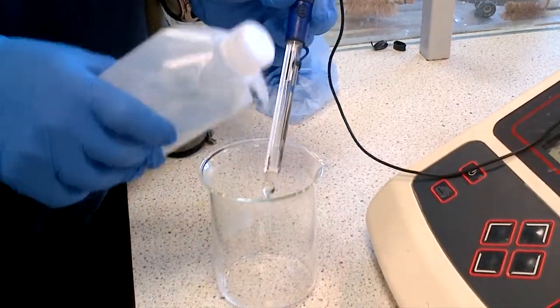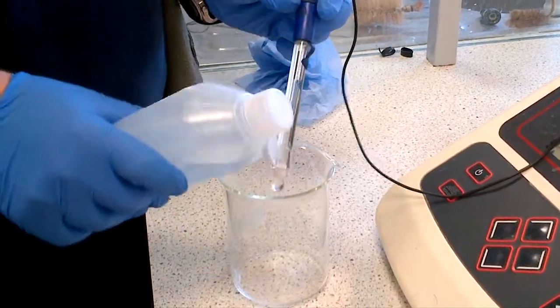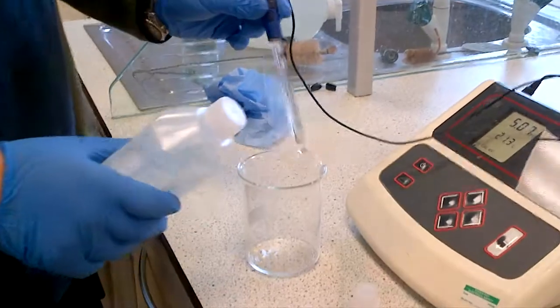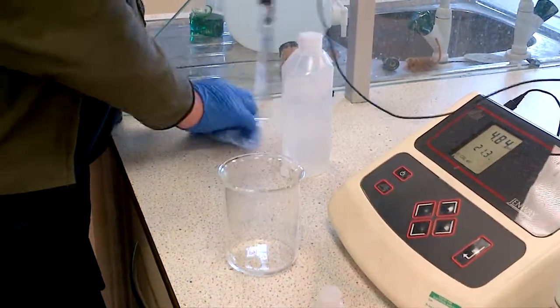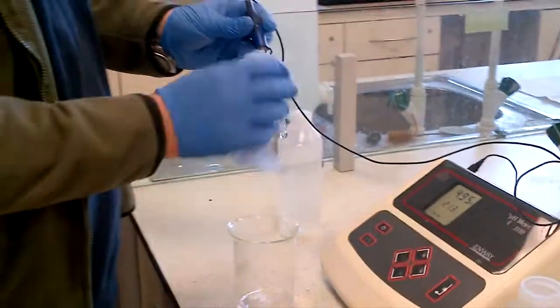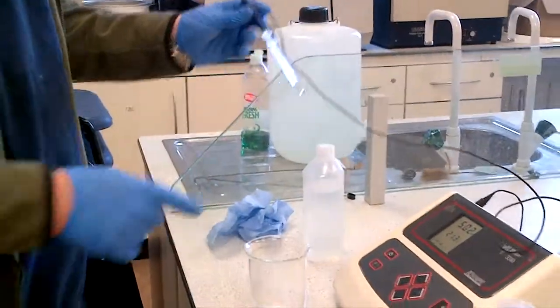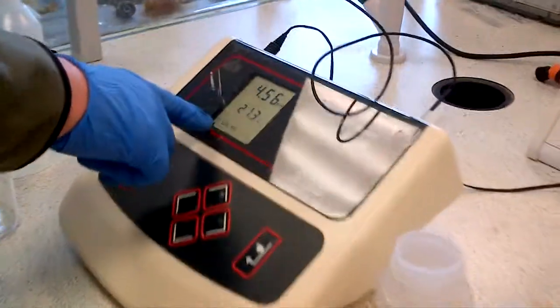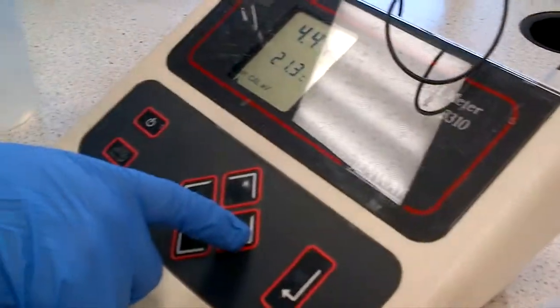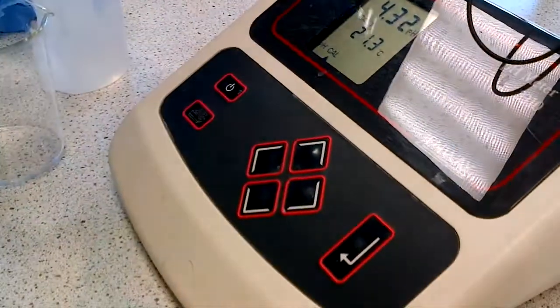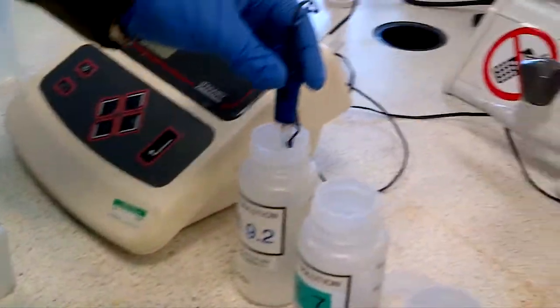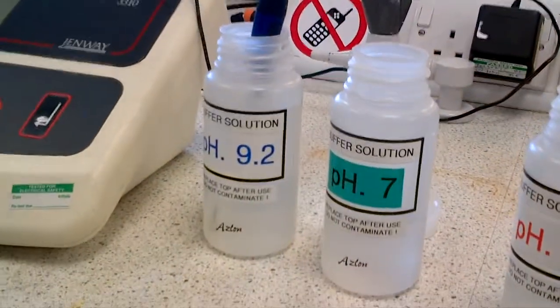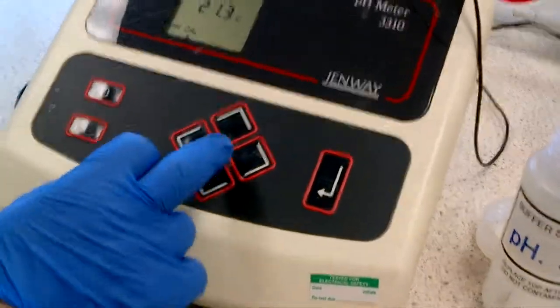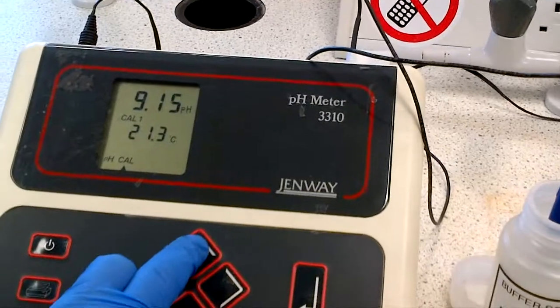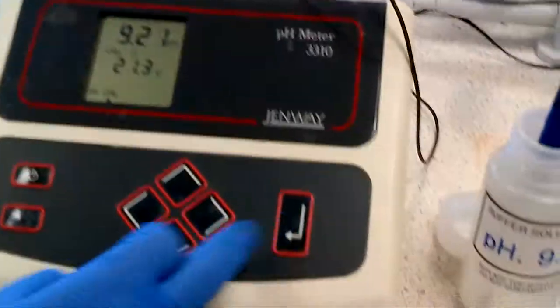We'll take distilled water and wash the electrode. We'll shake it over a beaker for washing, and sometimes, so as not to dilute buffers or other things, it's wise to take a fresh tissue paper and dry it. So let's go to the meter now and look at what we need to do. We can record pH or we can calibrate. We move this arrow to the right and press enter. We can calibrate it to the first buffer, so we'll place it into buffer 9.2. There are three buffers: 9.2, 7 and 4. With the arrow keys we'll make this 9.2, press enter, and that's the first calibration.